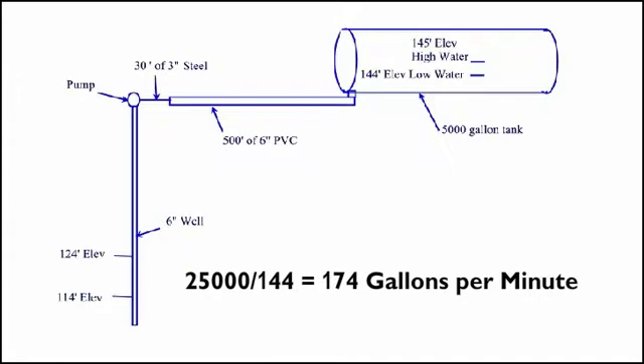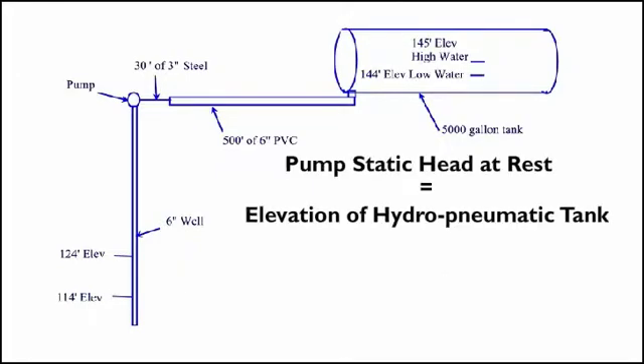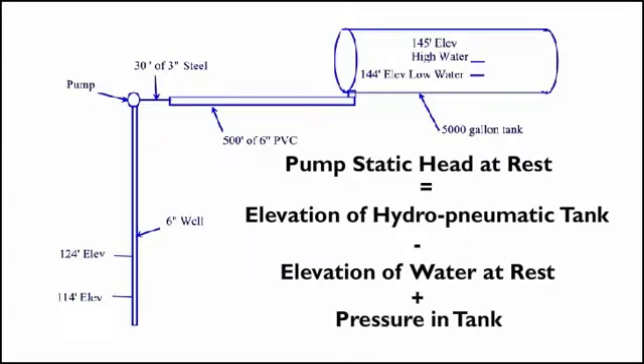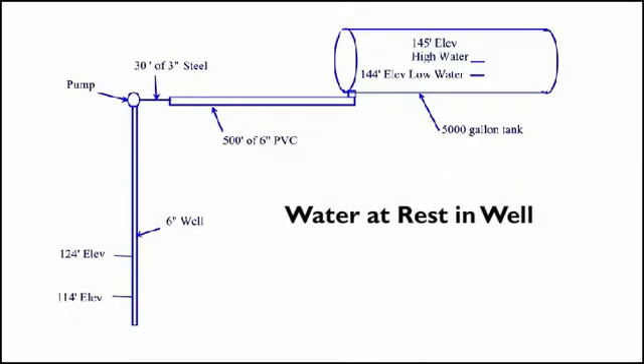To calculate the pump static head at rest, you have to subtract the elevation in which the water is at rest from the elevation of the hydropneumatic tank and then add the pressure in the tank. In this example, the water is at rest in the well at an elevation of 124 feet.